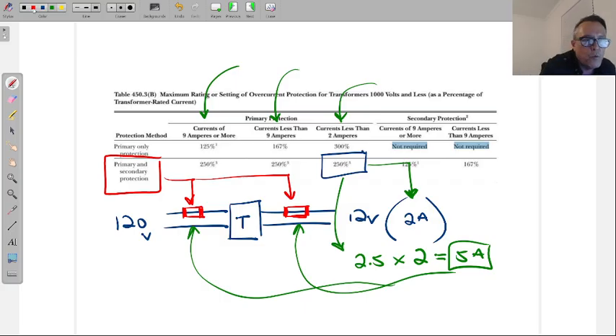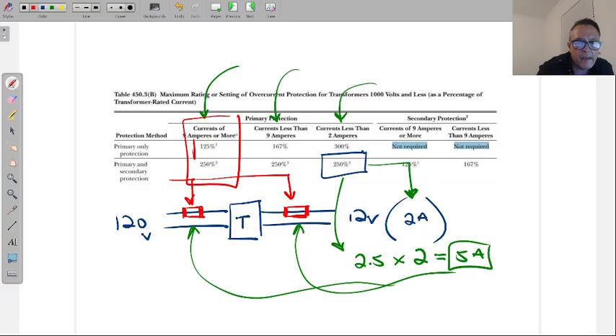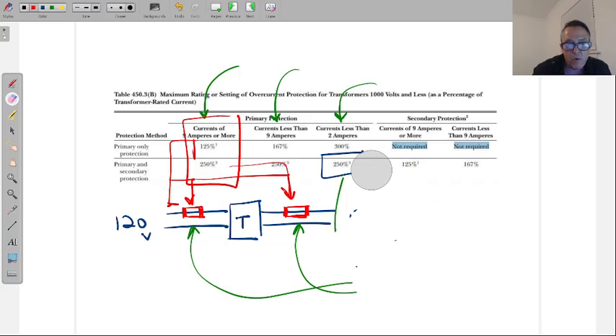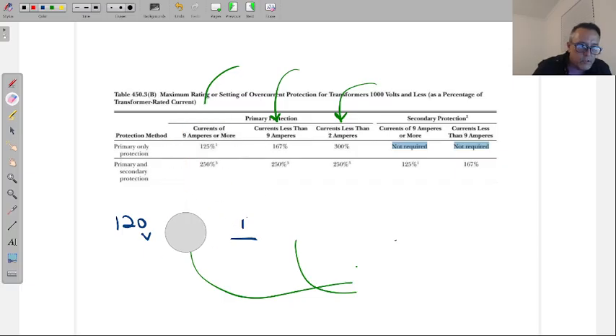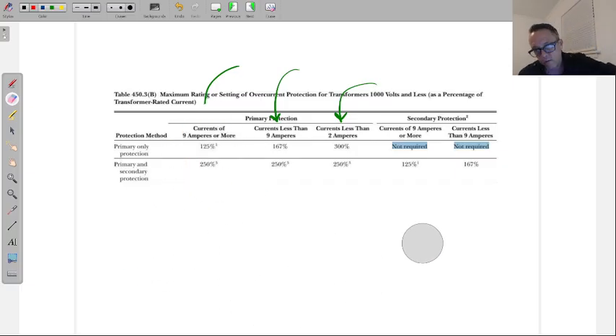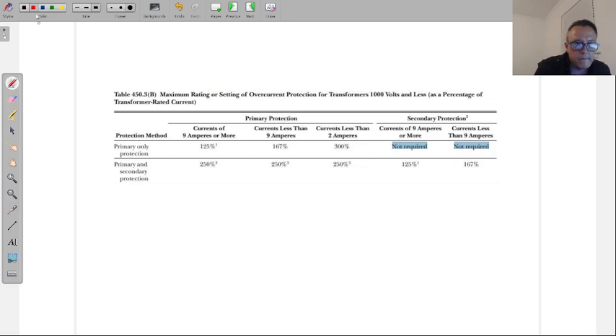And now any percentage along the way, you just match whatever it is that you're doing. All right, if you're only putting protection on the primary side and you're working or operating with higher than 9 amps, then 125% if you're only putting a fuse on the primary side. And if you're putting a fuse on both, then 250. And so, again, just some quick math. It's not going to come up, but I did want to explain, one, the focus of protecting the voltage going into the transformer. All right, you can protect both, but they really want to make sure we're protecting the voltage going into the transformer.